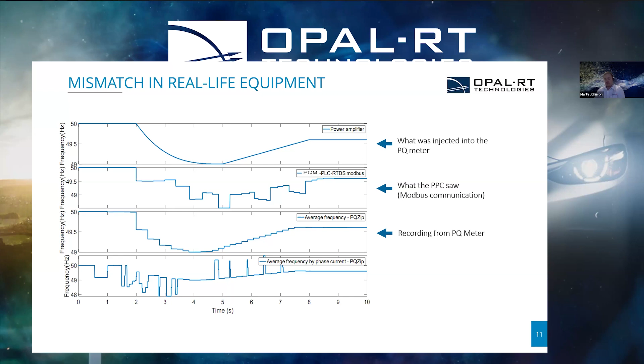But in reality, when we actually recorded, we still had the issue, so we had to troubleshoot further. We saw that the Modbus communication was different from the recorded information, and so the PPC was acting on this bad information, causing active power to swing around in directions we weren't expecting.